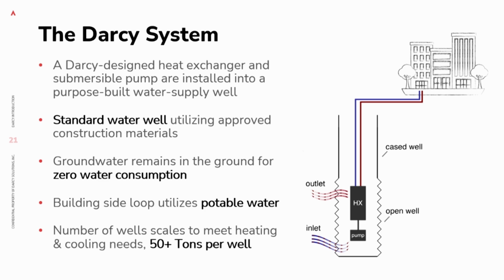On the other side of the heat exchanger, we connect to the building through a closed loop that uses just water, sometimes filtered or treated depending on the regulatory regime, since regulators don't take kindly to circulating glycol through an aquifer. Using just water also means less pumping energy and greater capacity to store and transfer energy. With this design, we see 50 to 70 tons of heat per well on the heating side, and 120 to 135 tons of cooling on the cooling side.